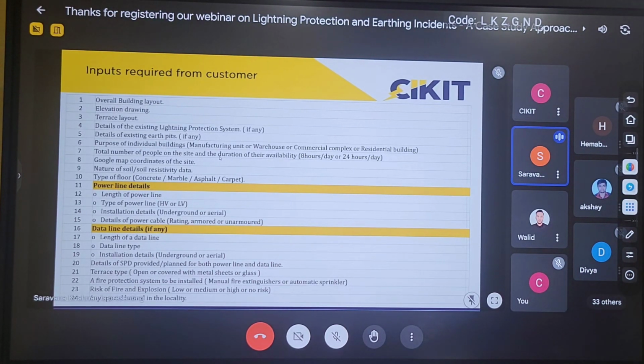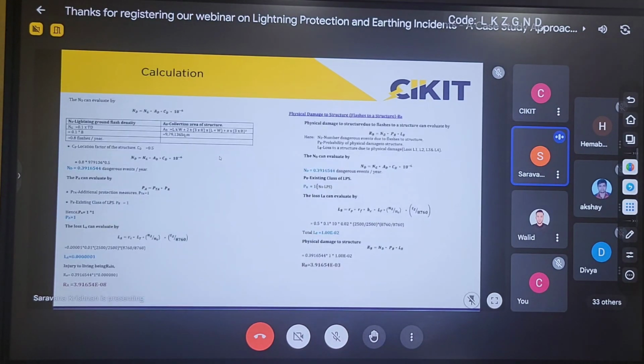I am just attaching a screenshot of this calculation. First thing is I have to calculate the value of each and every risk component. Here I have shown the calculation for RA and RB. The value of RA contains three parameters: ND into PA into LA. The value of ND is coming around 0.31, and the value of PA contains two parameters, PTA and PB. The PB is considered, and the value of LA is also calculated by performing the formula provided. If I perform it like this, the value of RA is coming around 3.91 into 10 power minus 8. Similarly, I am calculating the value of RB.